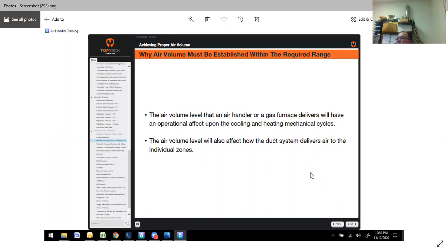This is huge. Why air volume must be established within the required range. The air volume that an air handler or gas furnace delivers will have an operational effect on the heating and cooling mechanical cycles, also comfort and noise. You can put the best furnace in the world in, but if it's not set up properly, the customer's going to start complaining on day one.